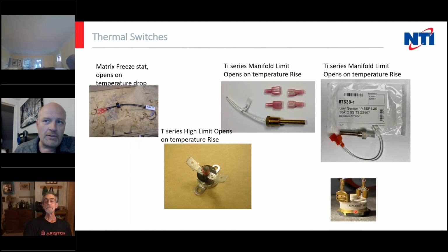And the reason we've gone away from bimetal strips to the extent possible is they're generally not as accurate or reliable as temperature sensors. So they're a little bit more prone to failure, especially if it's designed to be an operating limit, which means that every time the burner fires, it moves back and forth. Anything that moves has a limited life cycle count. And these were pretty high. I mean, they were probably 500,000 cycles, but certainly they would wear out more quickly than thermistors, which is what we're going to talk about next.